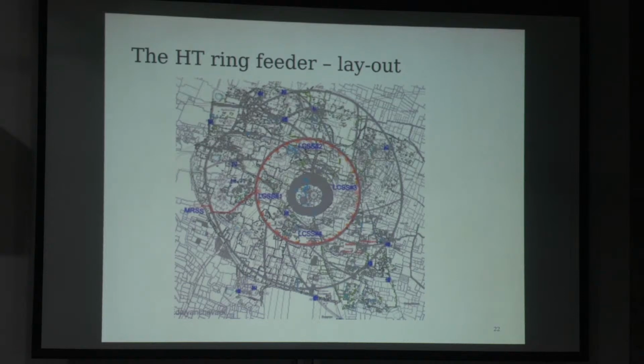Now, why do we do that? First of all, it is very difficult to justify financially that you invest now for 50,000 people in a ring. Second thing is, having 2 cables instead of 1 gives you more resilience. If tomorrow one cable would fail, you can do with a bit of load shedding, you can still feed the essential loads in Auroville. So finally, if this is the crown, there will be one high tension cable of 300 square mm on this side and one on that side. It is now a 22 kV cable, but you can operate, of course, a 22 kV cable at 11 kV, not the other way around.